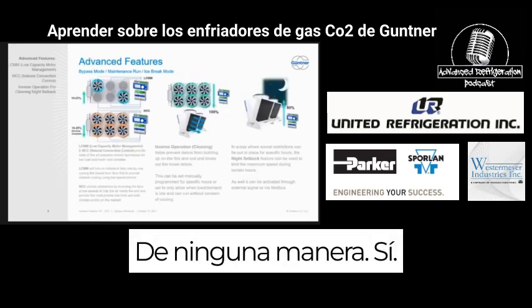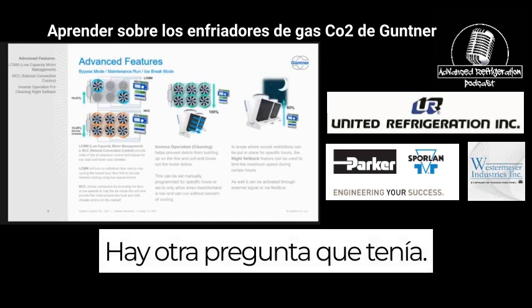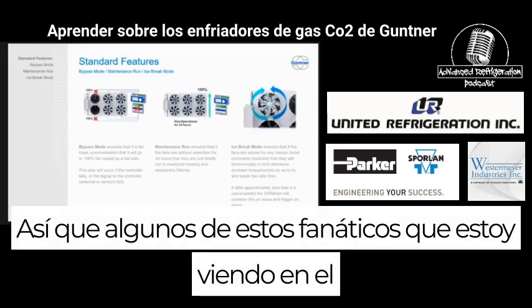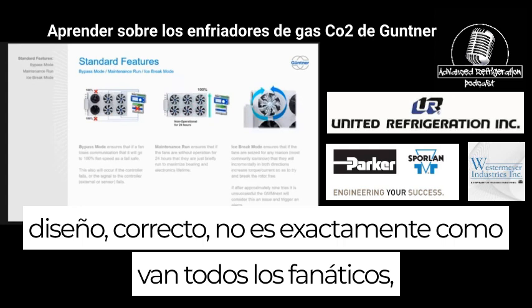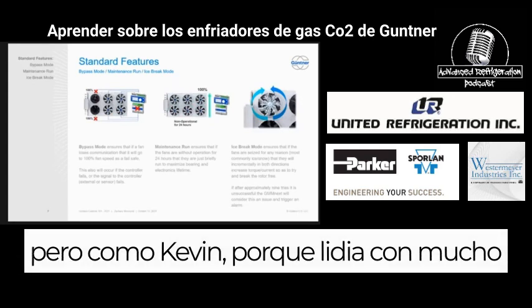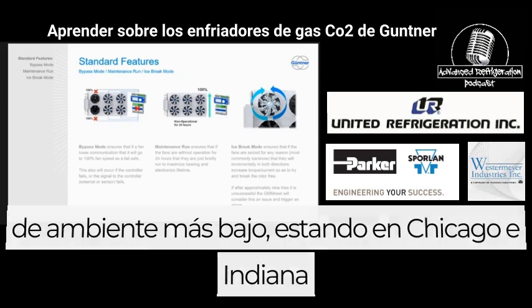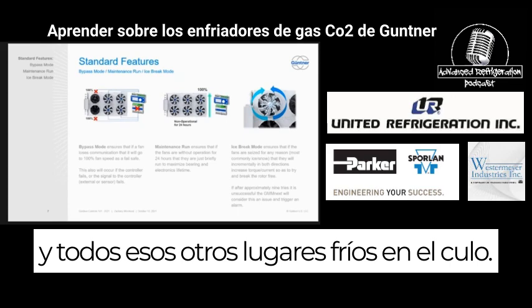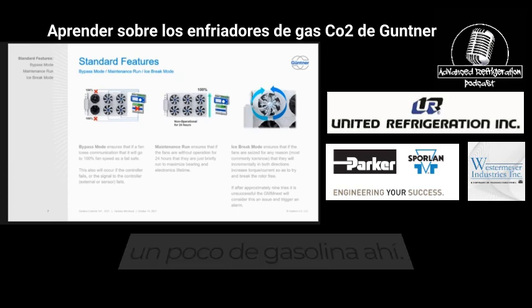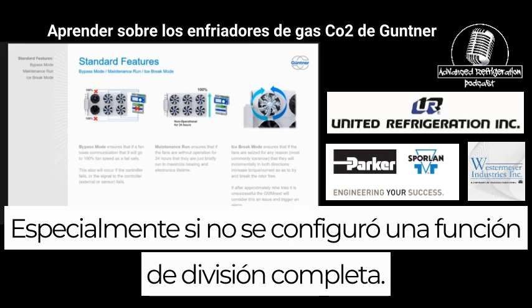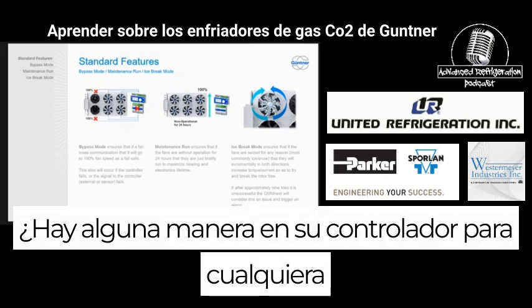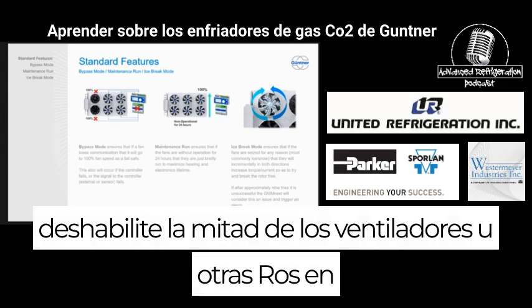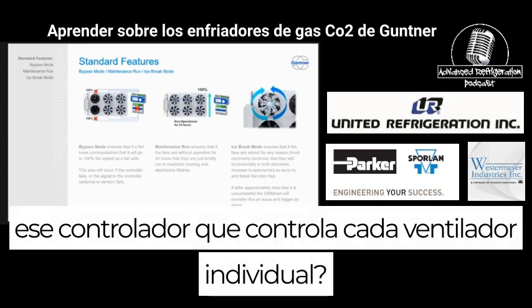No way. Yeah. So another question I had. I'm looking at the layout, and I know this isn't exactly how all the fans go, but Kevin deals with a lot of lower ambient, being up in Chicago and Indiana and all those other cold places, and a lot of times you'll start logging a little bit of gas in there, especially if a split function wasn't set up to be done. Is there any way in your controller to either disable half of the fans or other relay outputs on that controller that control each individual fan?